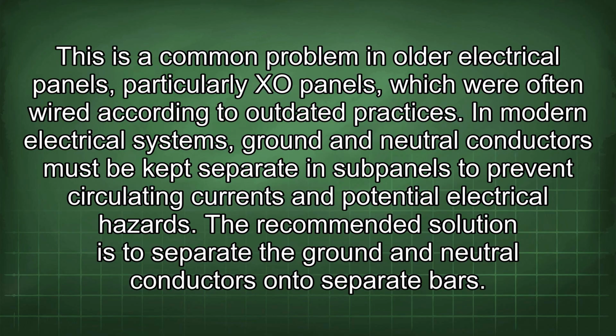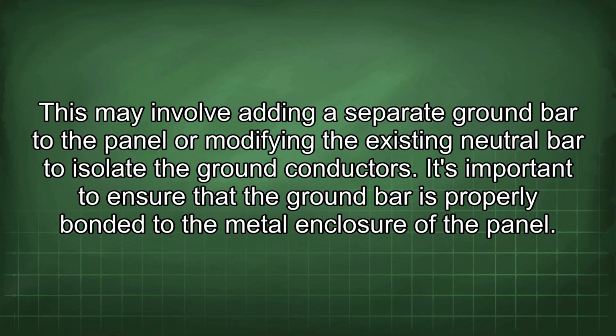This is a common problem in older electrical panels, particularly XO panels, which were often wired according to outdated practices. In modern electrical systems, ground and neutral conductors must be kept separate in subpanels to prevent circulating currents and potential electrical hazards. The recommended solution is to separate the ground and neutral conductors onto separate bars. This may involve adding a separate ground bar to the panel or modifying the existing neutral bar to isolate the ground conductors. It's important to ensure that the ground bar is properly bonded to the metal enclosure of the panel.